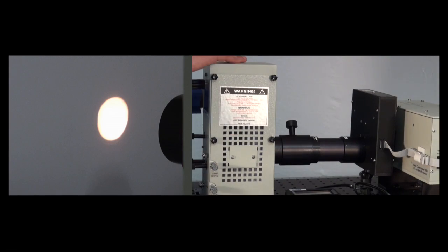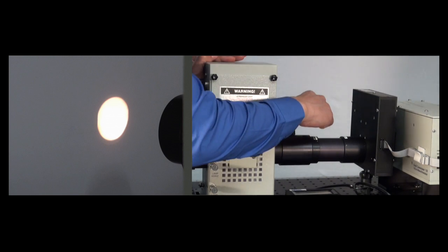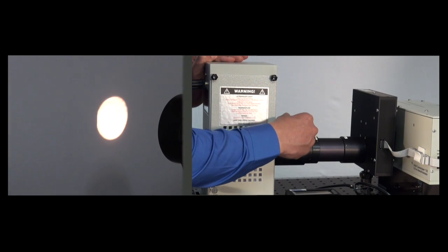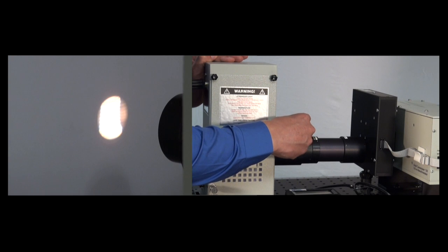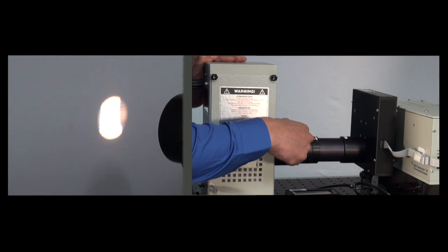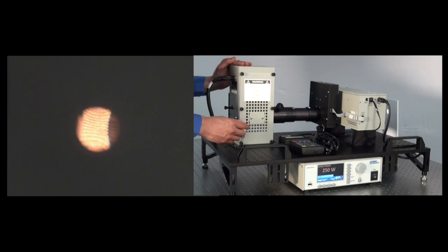So now we're going to adjust the focusing assembly. Using this we're going to turn it to the left to loosen it. This will allow the focusing assembly portion of the lens to move. Usually this is as close to the lamp housing as possible, but you're going to turn this knob and then observe on the backdrop. What you want is as clear of a filament image as possible.